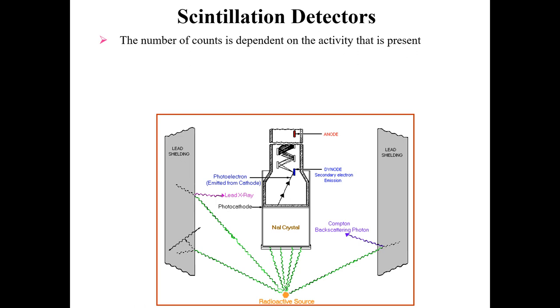When radiation falls on the crystal, the process begins. An electron is produced and carried to the dynode. Here we have secondary emission of electrons, which are made to fall on successive dynodes where they are multiplied until a sufficient number is detected by the anode and displayed on the screen. This is a straightforward process that one should understand.